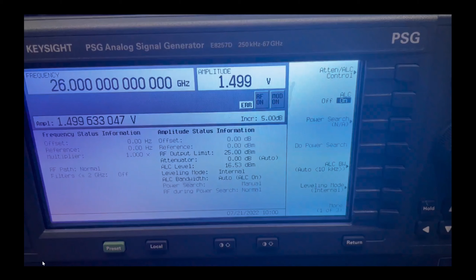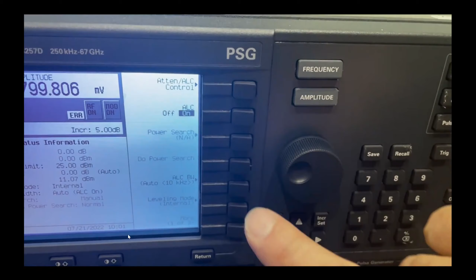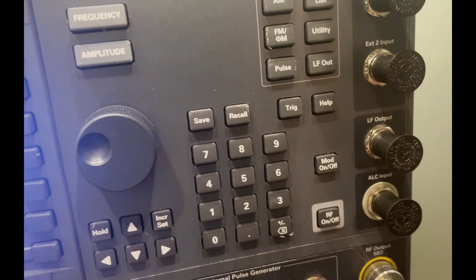So if you are doing this on a semi-regular basis, I would just recommend you have cabling or apparatus here that would match exactly what you're doing, so you don't have to keep removing these heads and changing them out just for the purpose of this calibration. Next, we want to get a general idea on the amplitude, so we can put it in free run mode. When we move along here, I'm showing that 26 gigahertz, 1.49 volt amplitude. And just for your interest, if a signal wasn't coming out when you're using the PSG, there's an RF out button on the bottom.